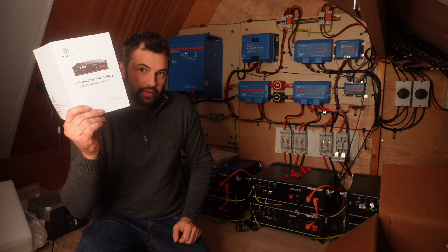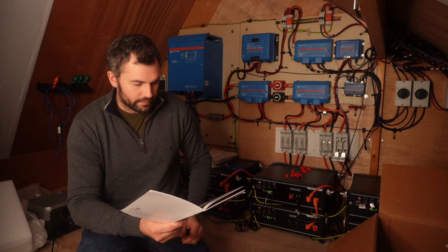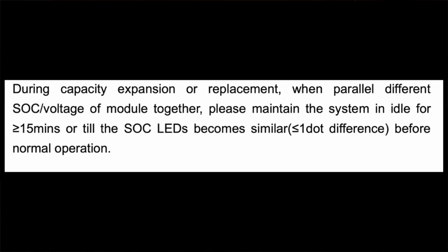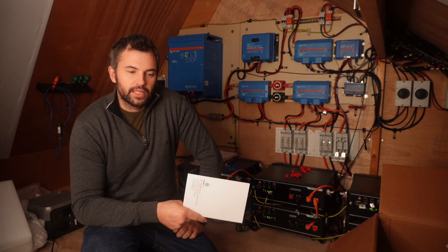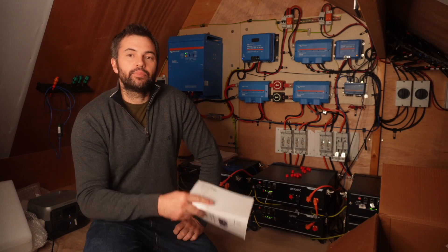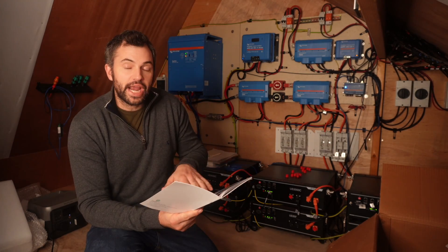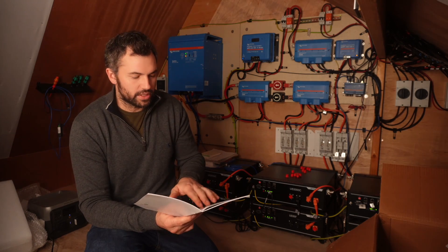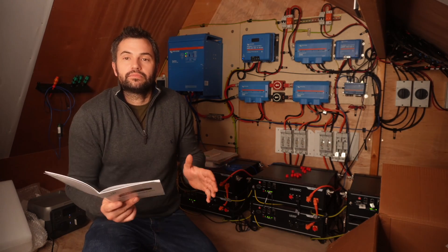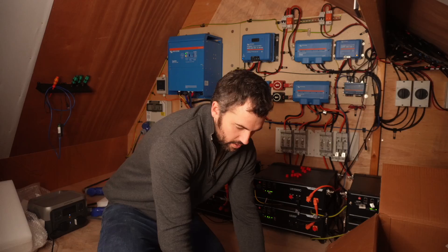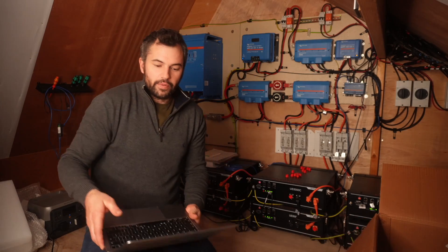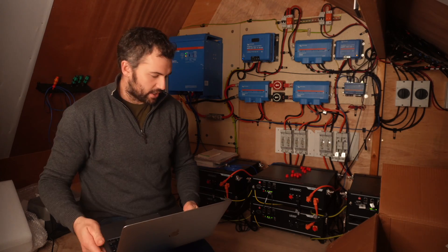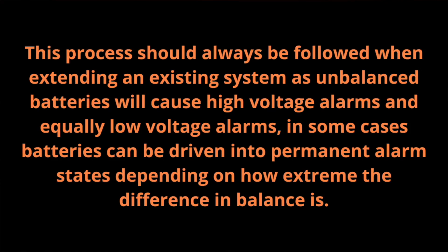The manual, the dreaded manual from Pylon Tech. Now it says here during capacity expansion or replacement, when parallel different SOC voltage of modules together, please maintain the system in idle for 15 minutes or till the SOC LEDs become similar, one dot difference before normal operation. They don't say anywhere to charge these to 100% and then put them together in this manual. In fact, that suggests to me that they sort themselves out, they balance themselves, that they do move around. But they don't.